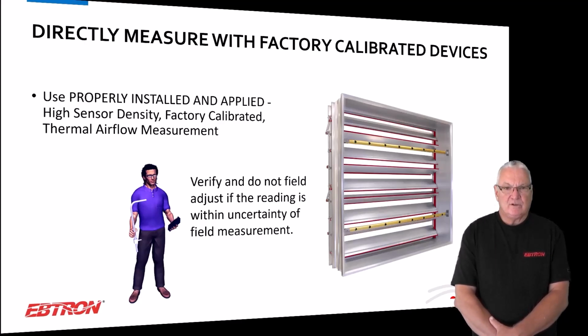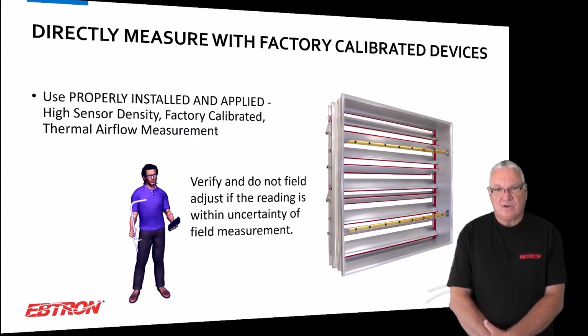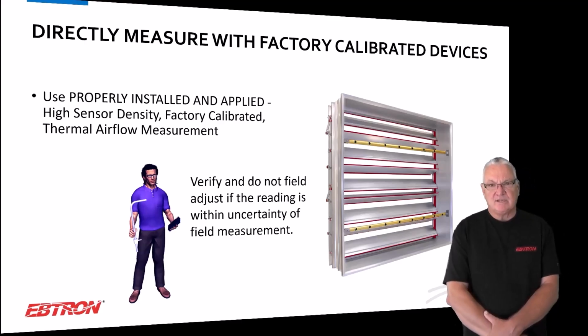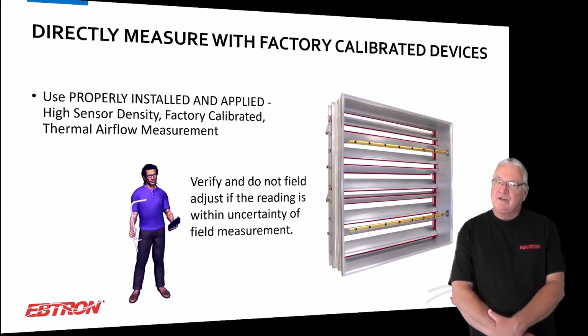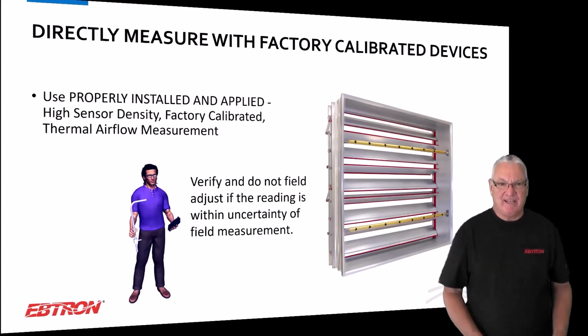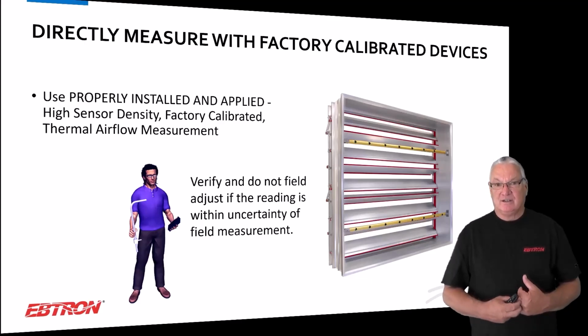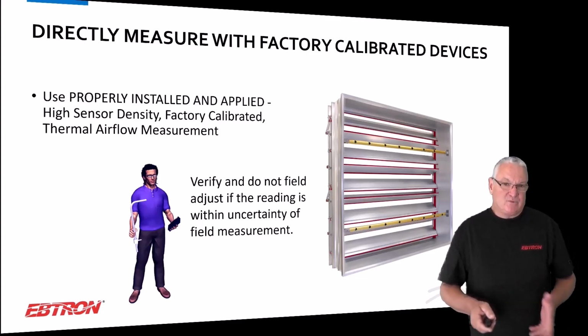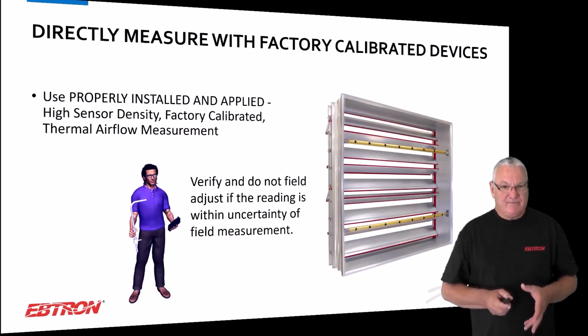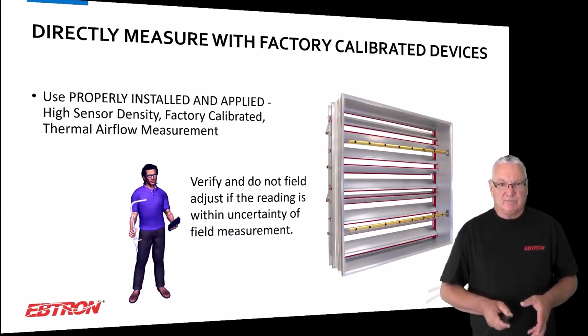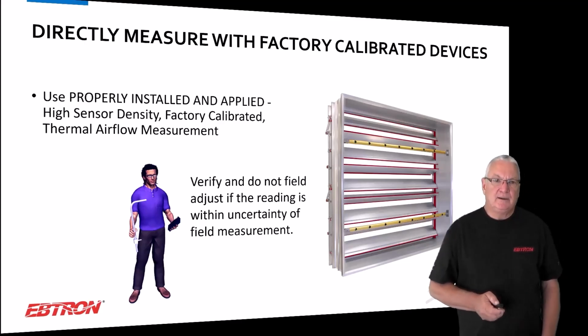And I tell people all the time, if you have critical air paths, and you're concerned about dirt and dust accumulating on your dampers and your flow meters and everything else, then why are you bringing that outdoor air in? Okay, you really need to think about maybe doing something to make that air in a better condition. We do lots of outside air flow meters a year, and the reality is some of them do get pretty fouled up, but not most of them. But if you have that bad of a condition coming in, don't shoot the messenger, fix the condition, okay? But anyhow, that's what I want to say about that. The bottom line is, a 5 or 10% outdoor airflow meter blows away any other method, okay? So that's my position there.